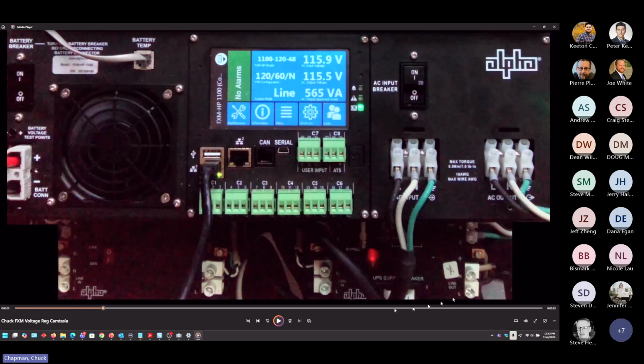One is on this side, the automatic transfer switch that takes the utility in, provides a bridge up to the FXM, then takes the output of the FXM and runs it back through this bridge. In normal operation, it provides power to the FXM and then takes the power from the FXM and gives it to the load. But if something were to happen to the FXM, it will directly connect the input to the output, not creating an outage. Our transfer time on the FXM is less than 3 milliseconds, so it generally can't be detected at all. It's a good thing.